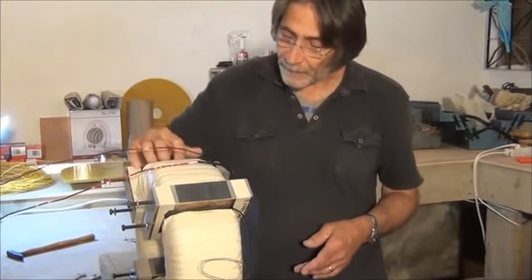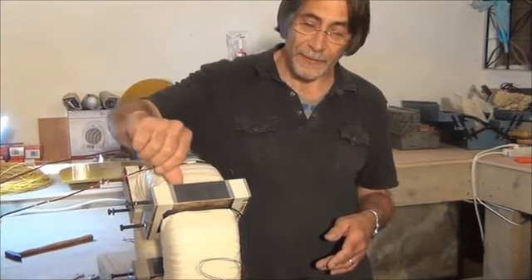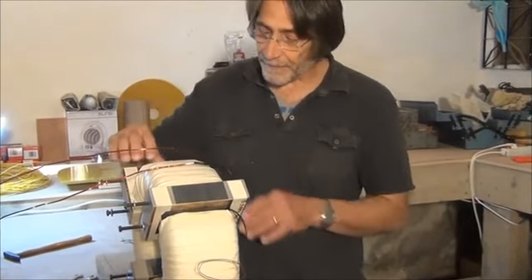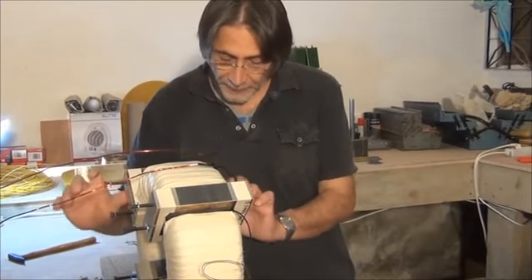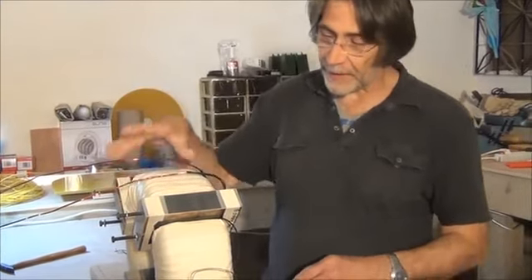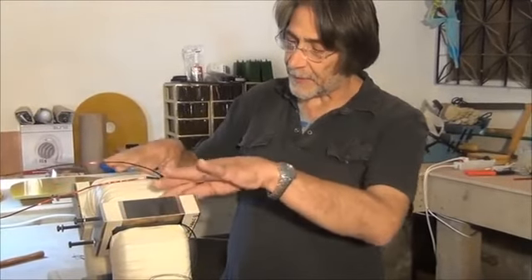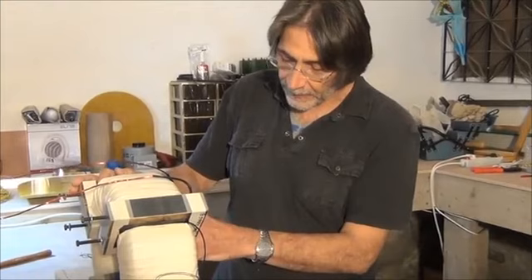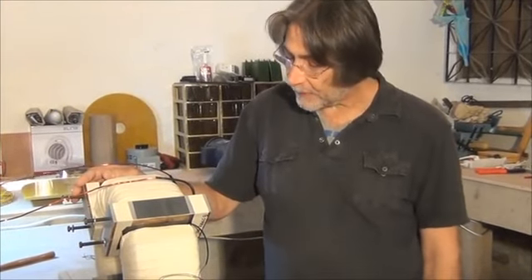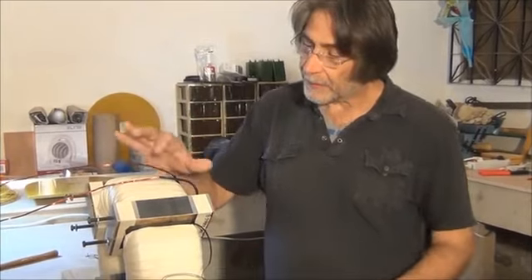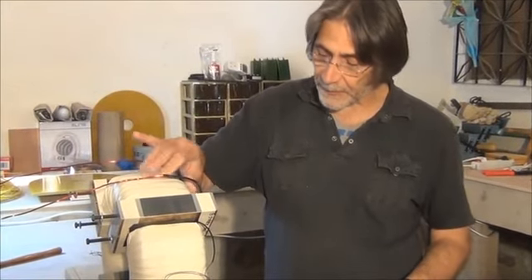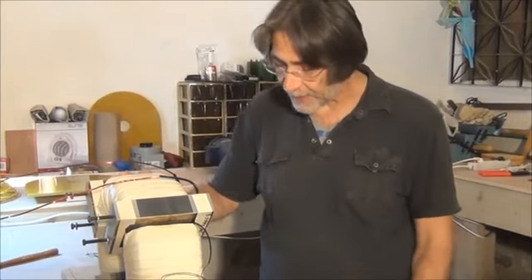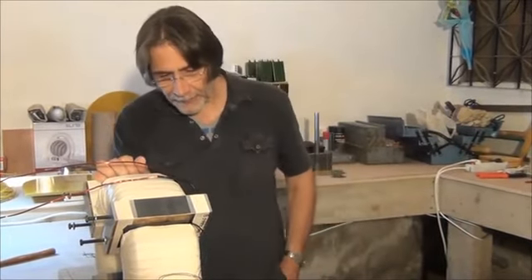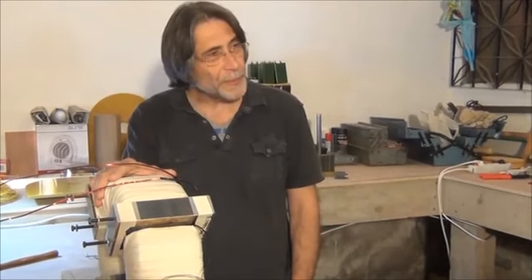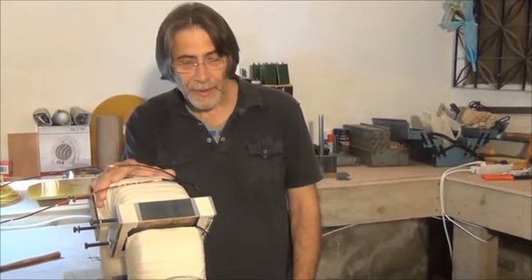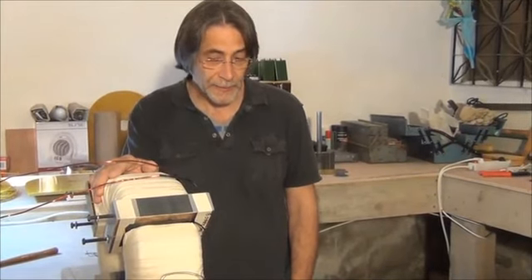And then there are plates made of 30 thousandths thick mica plate covering each of the pole pieces on both sides where the wire is in contact with the pole piece. There's mica plates on each of the four faces of the pole pieces. And then the outer wrap is just fiberglass tape to protect the outside of the wire. This was only the third one that was built this way. And at this point, we changed the insulation system.